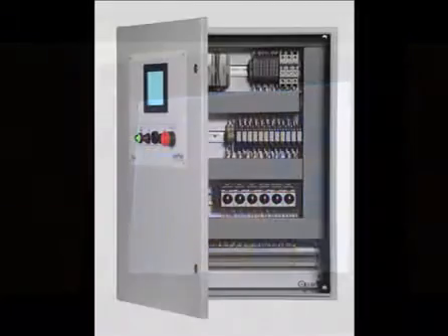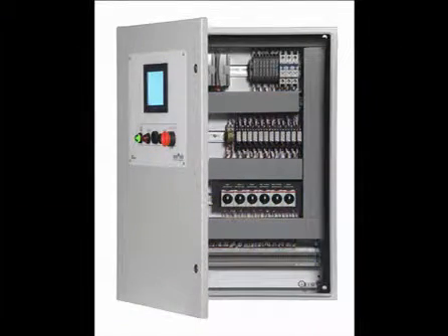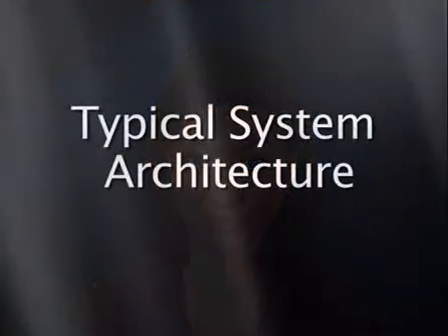The screen presents information in an organized way with the important operation status for the fuel system and any alarm conditions requiring immediate attention. The sequence of operations is the heart of the PLC system. This is a written narrative describing how the system works, which includes responses to failed system elements. The sequence of operation may be prepared by the system design engineer or by the fuel system specialist for engineer review and approval.